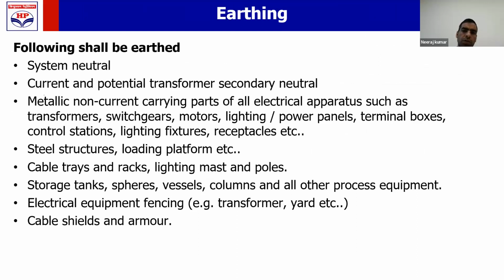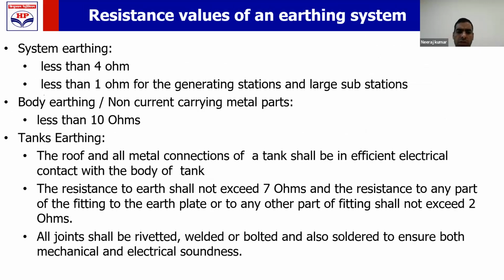Earthing, it is also a general requirement that system neutral, CT and PT, non-current carrying metallic parts, all steel structure, cable trays, storage tanks, vessels, columns, all other electrical equipment and cable armor, all these shall be earthed. I'm not discussing in detail because most people know this. Resistance value. For the system, 4 ohm is enough. If you have a huge substation or generating station, your system earthing resistance would be 1 ohm or less. For tanks, 7 ohm is acceptable.